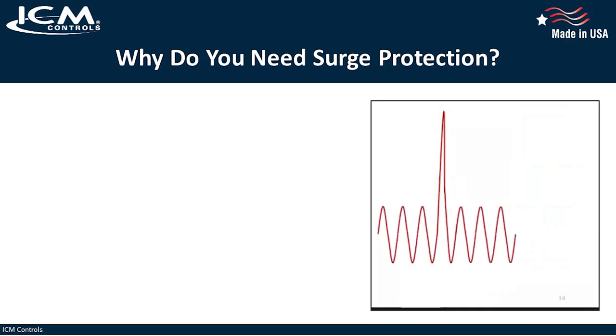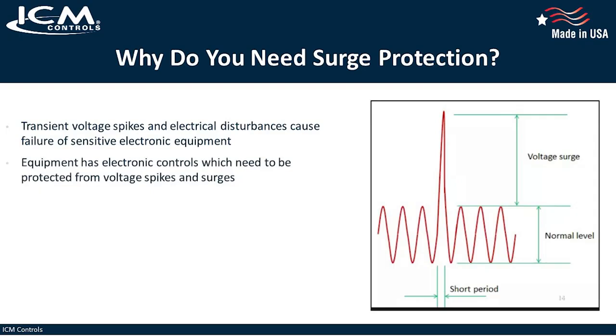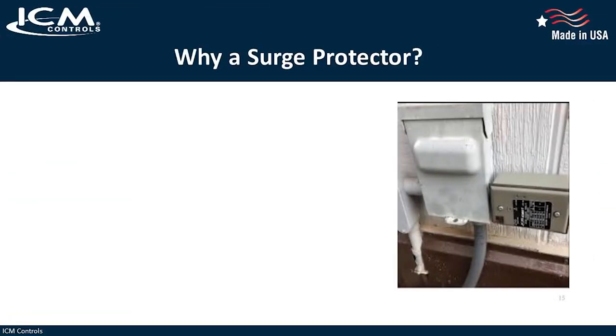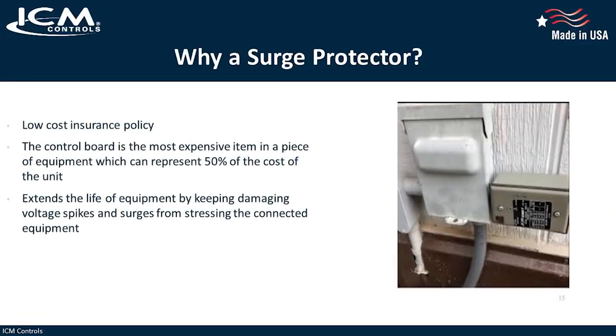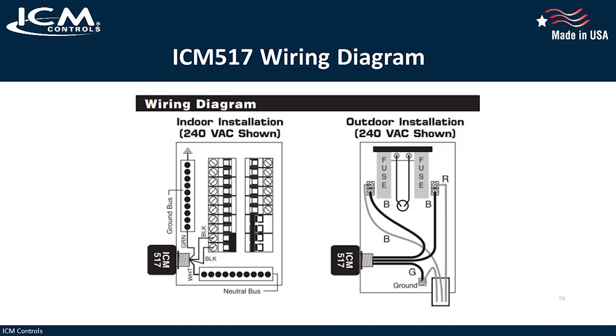A surge, or transient voltage spike, is an electrical disturbance that lasts only for a very short duration, but can be very damaging. Powerful enough to fry your sensitive electrical equipment. Like a line voltage monitor, a standard surge protective device is usually wired in parallel with the equipment it is designed to protect. For a Type 2 device, like the ICM 517, it's important to note that the unit needs to be installed on the load side. Whereas a Type 1 device, which is commonly referred to as a whole house device, can also be installed on the line side.